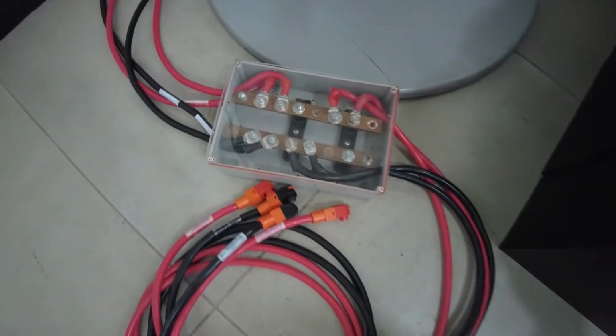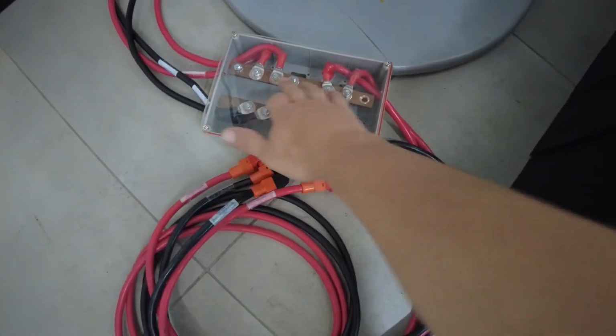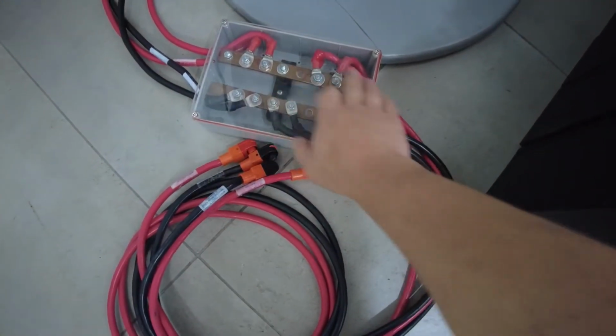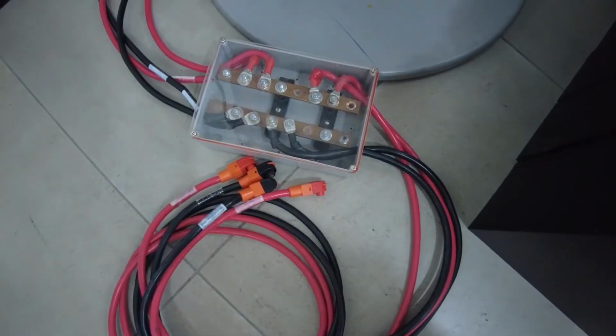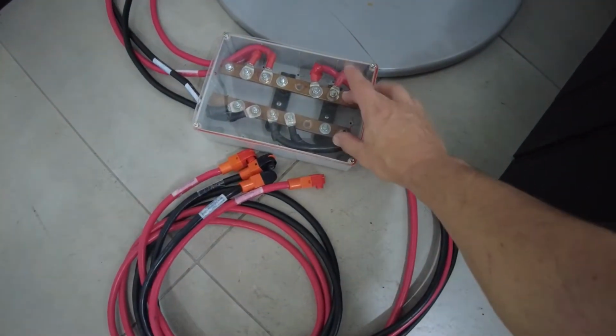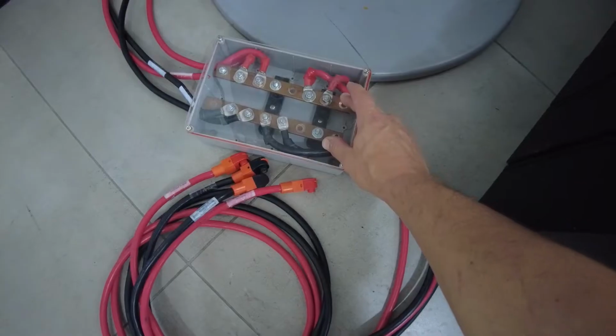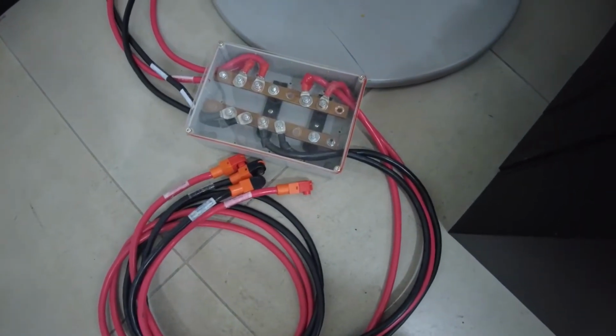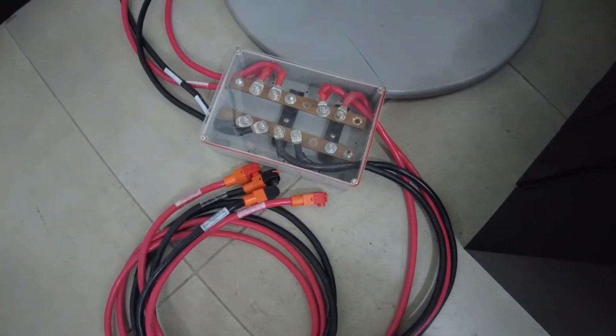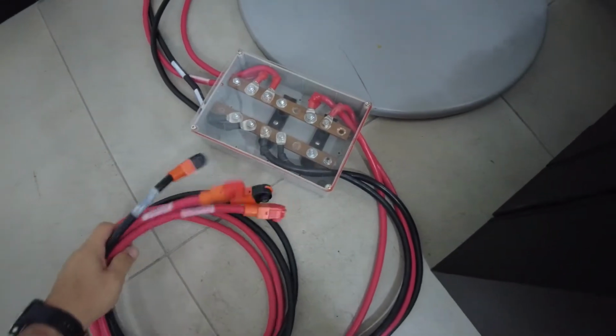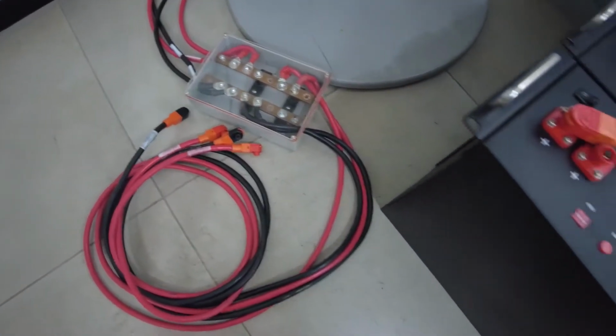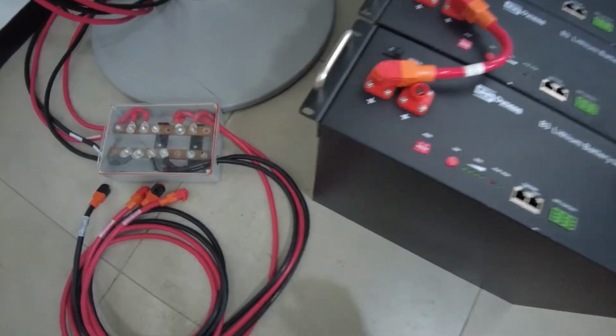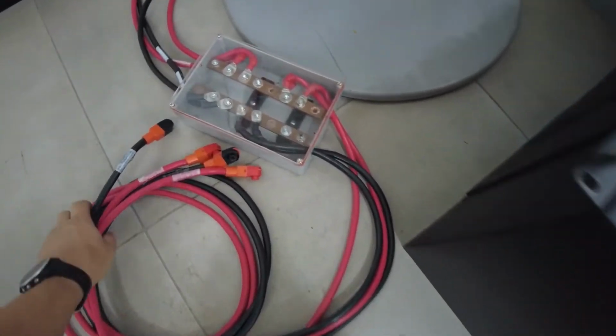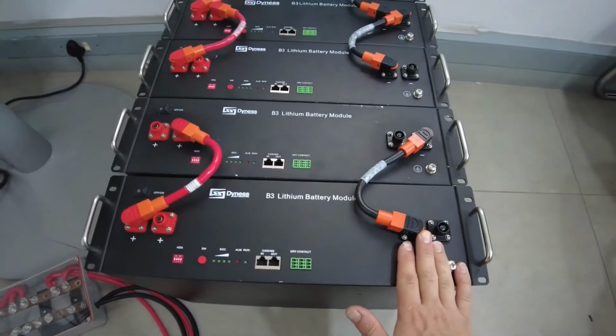Now in this case, because we use a combiner box, you have your bus bars. Generally all of the cables will share an even amount of power. Your 2 bus bars are handling the majority of the load. So you should have an even amount of power on these cables. So you should not worry too much about which cables you connect where, as long as you still connect across the batteries.